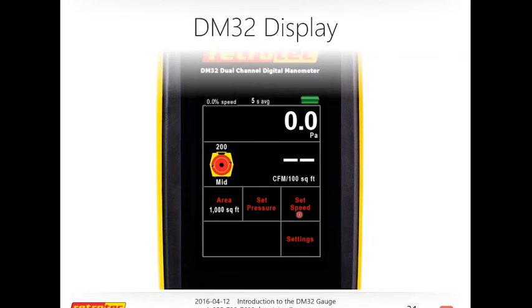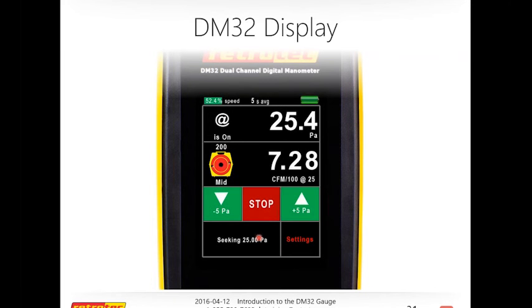Now if you start to run a test, the screen changes, and this is what it looks like during a test. In this test I am doing a CFM per 100 at 25 pascals, and I've told my gauge to tell the fan, hey, seek 25 pascals, and I'll explain how to use that.